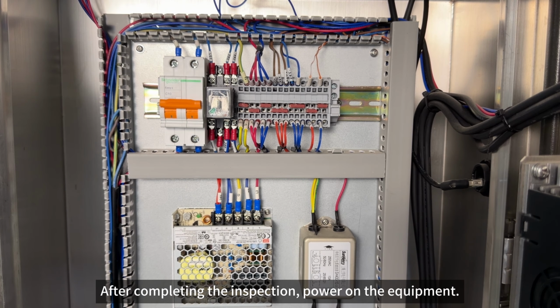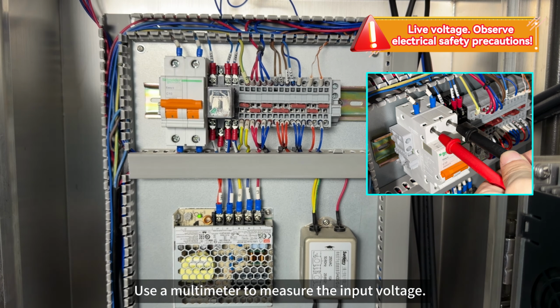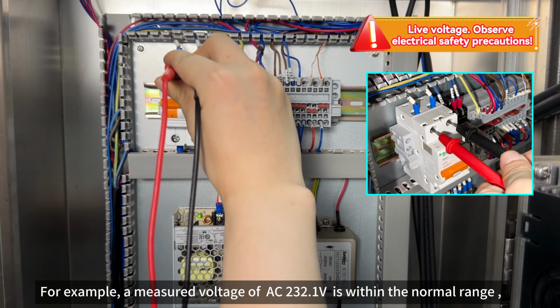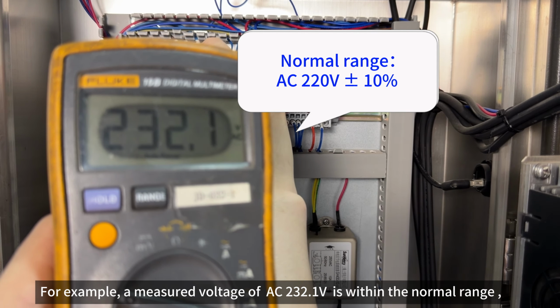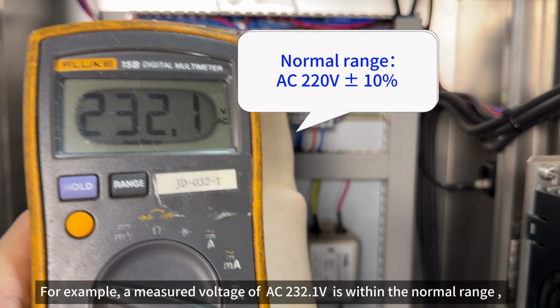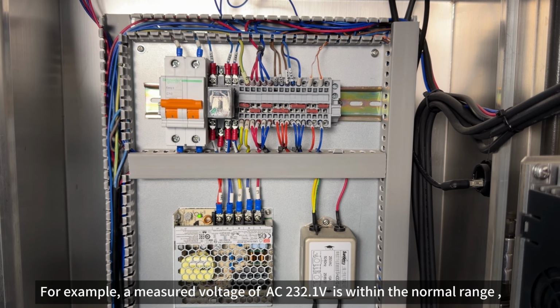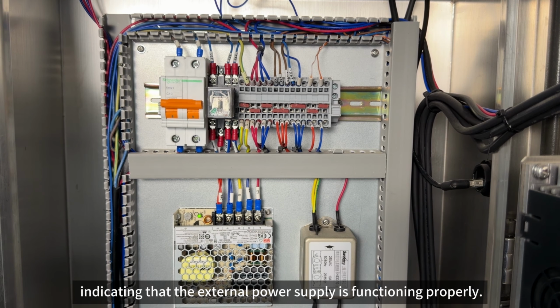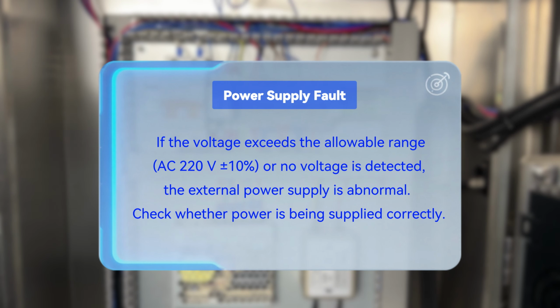After completing the inspection, power on the equipment. Use a multimeter to measure the input voltage. For example, a measured voltage of AC 232.1 volts is within the normal range, indicating that the external power supply is functioning properly. If the voltage exceeds the allowable range, AC 220 volts plus or minus 10%, or no voltage is detected, the external power supply is abnormal. Check whether power is being supplied correctly.